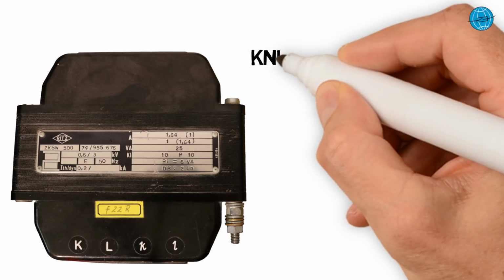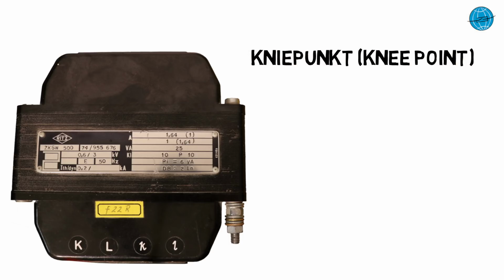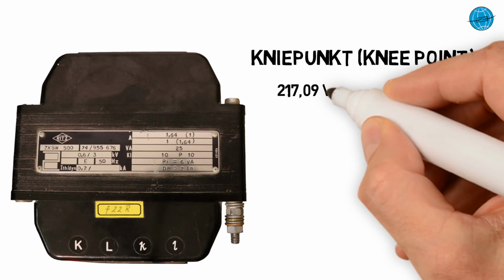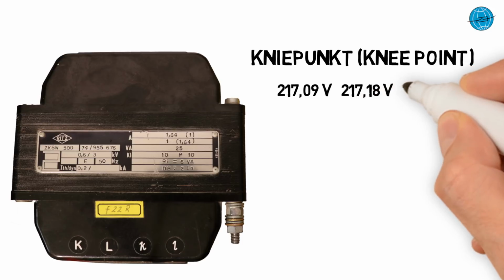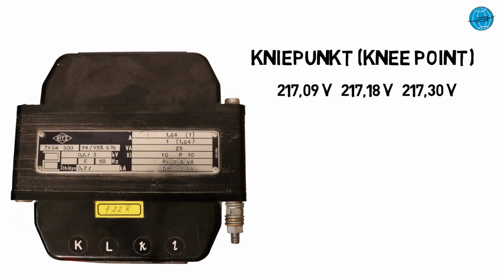We were able to get the following results. The 3 measurements of the knee point voltage of our starting CT provided the values 217.09, 217.18 and 217.3 volts.